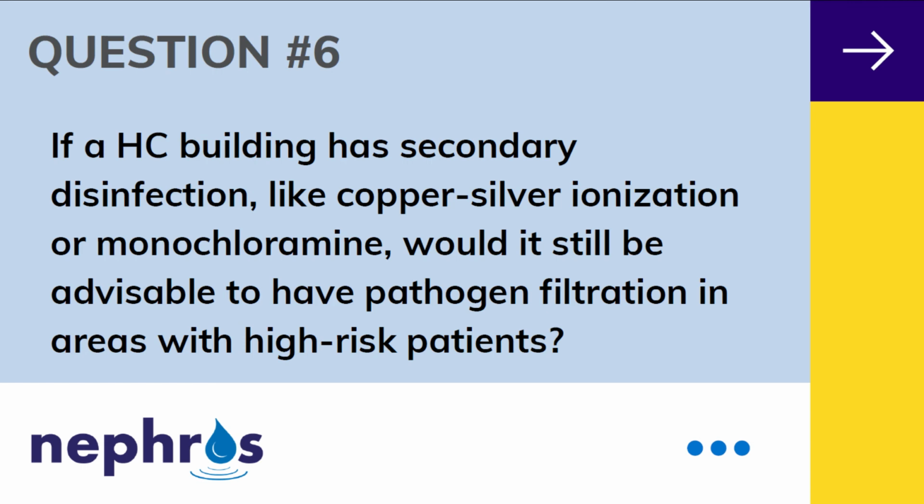So we may have those water free floating bacteria, planktonic bacteria, coming off the biofilm source, and that biofilm has a potential for opportunistic bacteria adapting resistance due to the fact that the biomass has so many bacteria that can change. So the filtration would offer an additional protection from times of low water disinfectant or even times of stagnation as they try to start up, let's say, an inactive room that's been empty for some days.